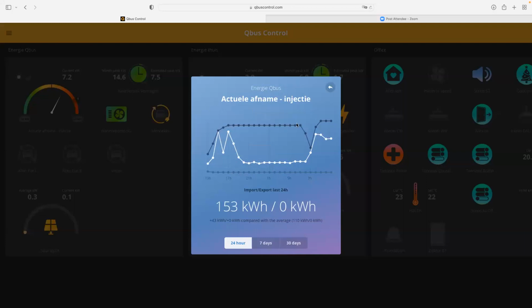The black line is the maximum limit we've set. We've set a maximum limit to purchase no more than 17.5 kilowatts from the grid for our company. You can see the white line following pretty closely the maximum we've set.